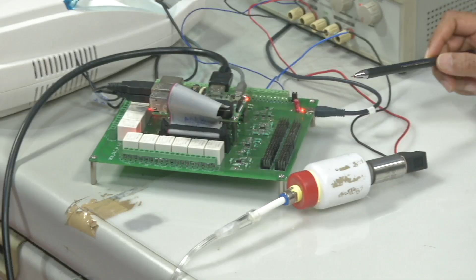Now the point is, if you set it to some pressure, the pressure transducer should be able to make a measurement and allow the nebulizer to stay on until it is within a given threshold. After that it has to cut off, and switch on again all by itself, so that you are always maintaining a certain pressure. Now how do you do that? That part is done by this little board that you see here.